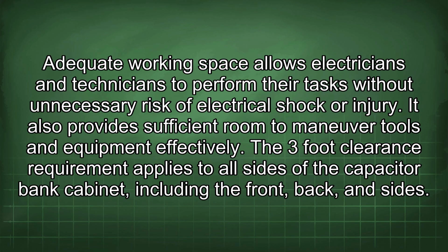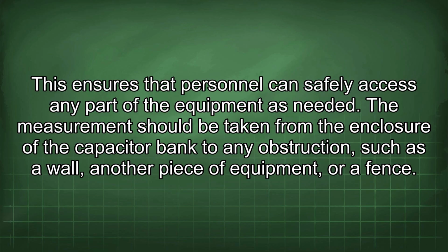The 3-foot clearance requirement applies to all sides of the capacitor bank cabinet, including the front, back, and sides. This ensures that personnel can safely access any part of the equipment as needed.